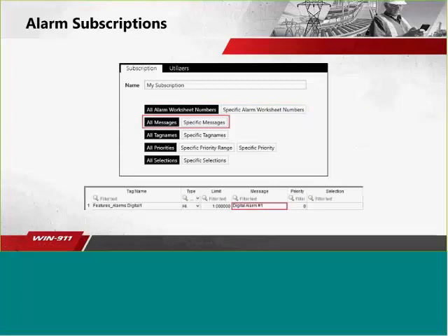I can also filter on the message field. So I can create a wildcard filter on the message field. In this example, if I wanted to pull in this alarm that is in the screenshot at the bottom, if I chose specific messages and typed in the word digital, any alarm that goes active that has the word digital in the message would match this subscription and would come into WIN911. You can also do this with tag names. Same kind of deal with a string wildcard.